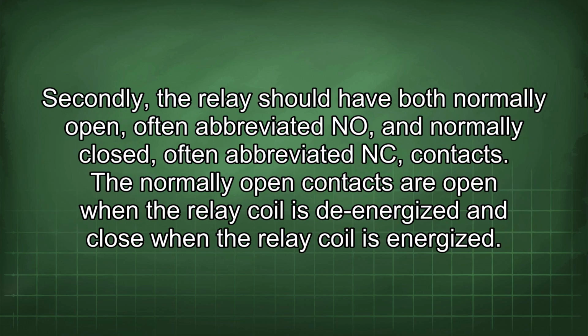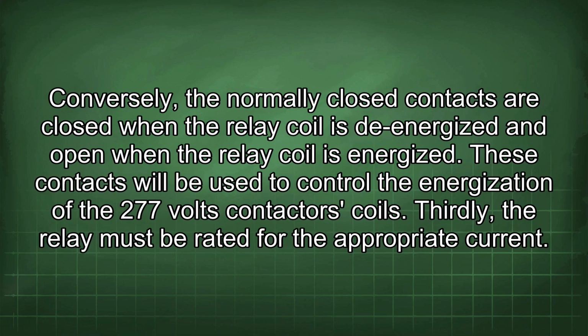Secondly, the relay should have both normally open, often abbreviated NO, and normally closed, often abbreviated NC, contacts. The normally open contacts are open when the relay coil is de-energized and closed when the relay coil is energized. Conversely, the normally closed contacts are closed when the relay coil is de-energized and open when the relay coil is energized. These contacts will be used to control the energization of the 277 volts contactors coils.